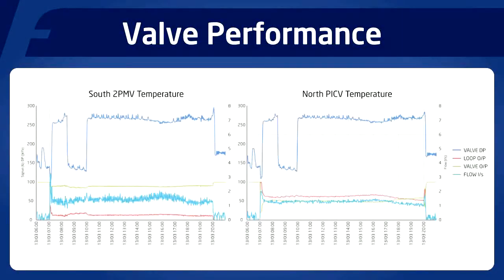Once again, after 2 weeks, we reversed the position of the pressure independent control valve and the conventional two-port modulating valve. Here we can see the valves both regulated the flow fairly well during an anomaly when the pressure across the valves dropped for a period from 270 kPa down to around 140 kPa. Of course, in the right hand pressure independent control valve, this was achieved through the differential pressure controller operating, and on the left hand two-port modulating valve we can see the stem position increase from around 10% open to around 20% open to maintain a fairly stable flow, but through the changed stem position of the valve.